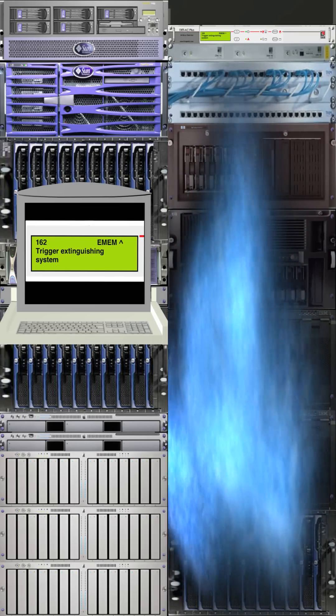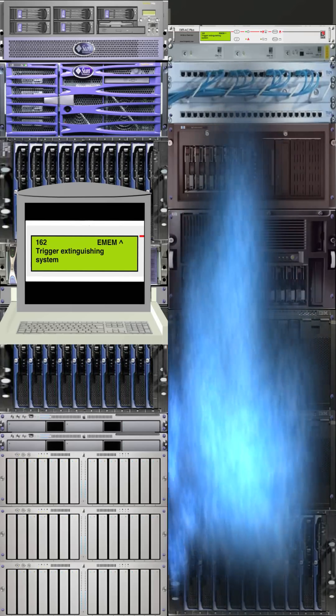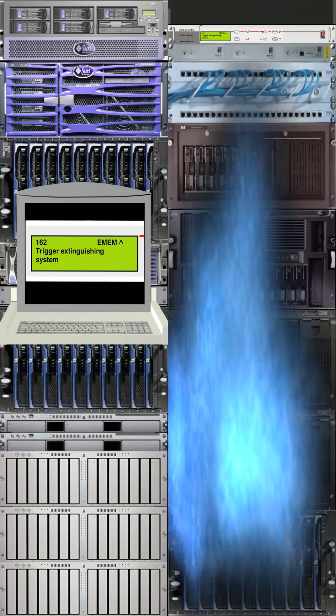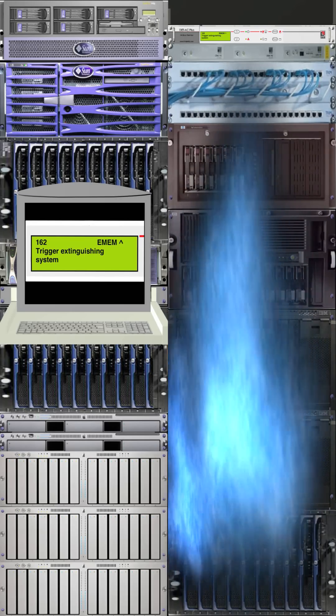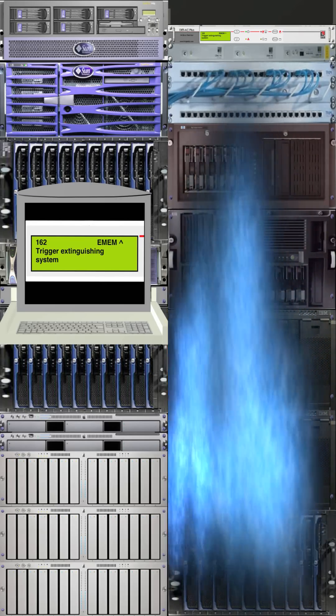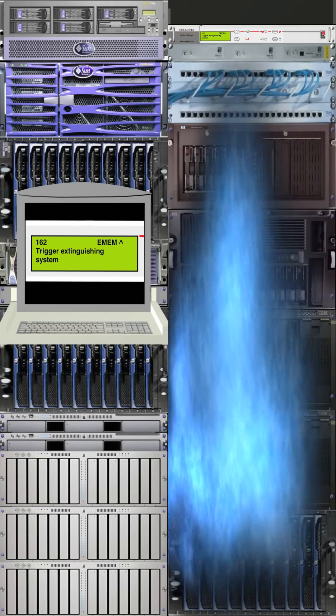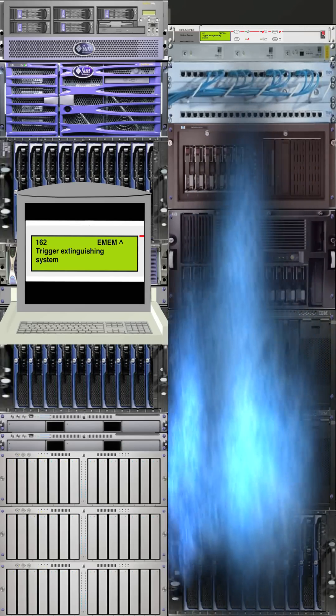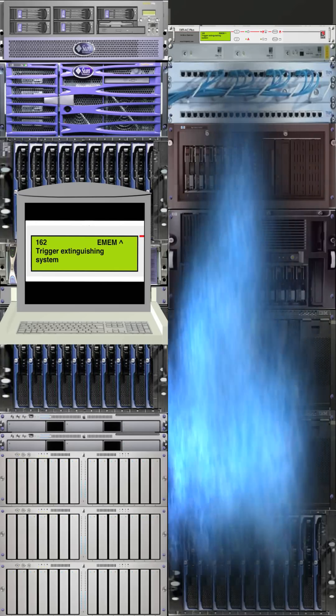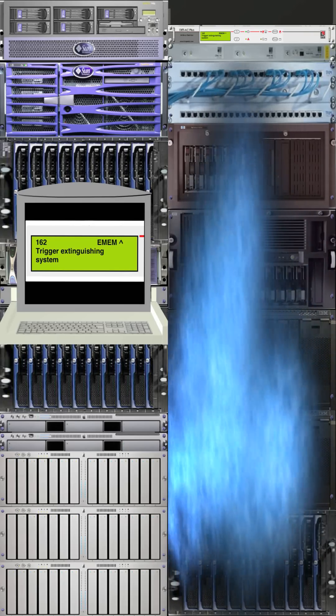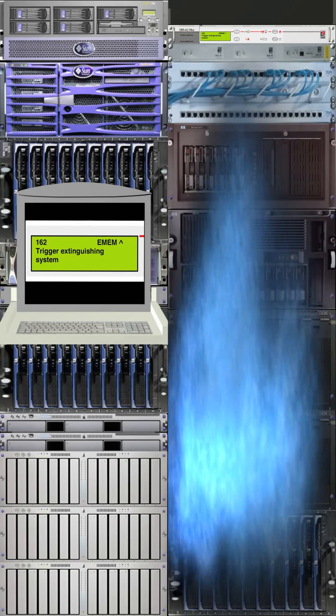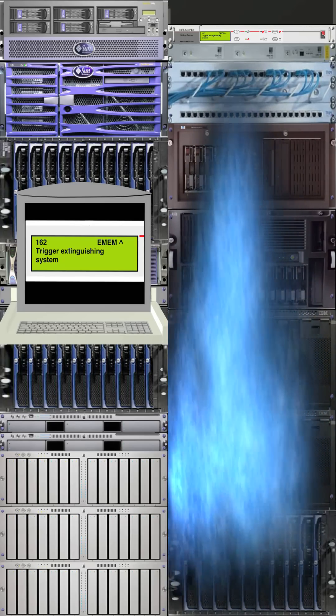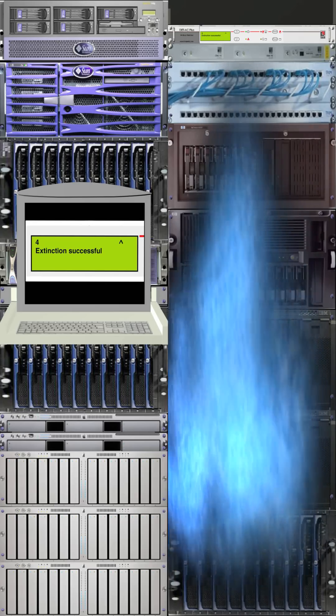The eco-friendly Novec 1230 fluid has zero ozone depletion potential and the lowest atmospheric lifetime for halocarbon, five days. The closest alternative is 33 years. It has a global warming potential of one, 99.9% lower than any halocarbon agent acceptable for use in occupied spaces. Novec 1230 fluid has the greatest margin of safety for use in occupied spaces. It makes good business sense to use Novec 1230 fluid because it's a sustainable, long-term technology. Not only does Novec 1230 fluid meet today's regulations, but sensitive hardware such as servers, storage and switches aren't impaired by the extinguisher medium.